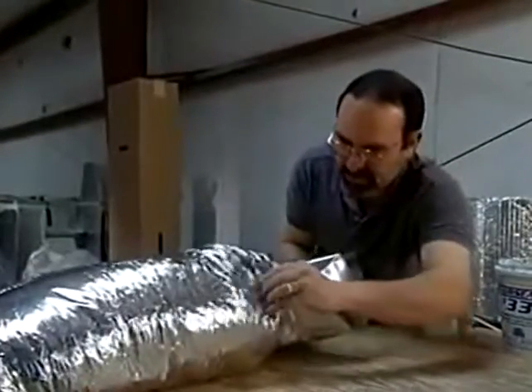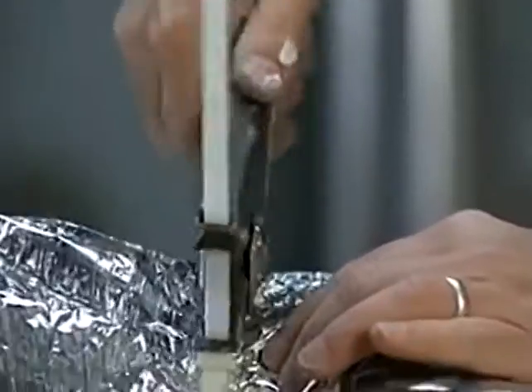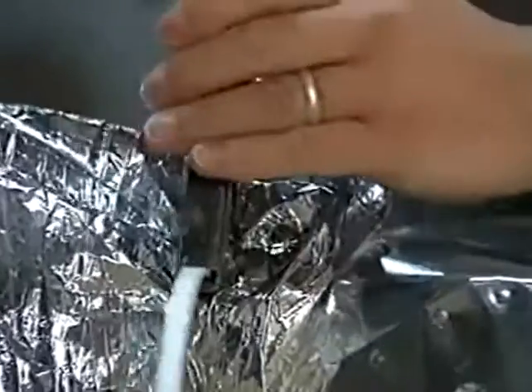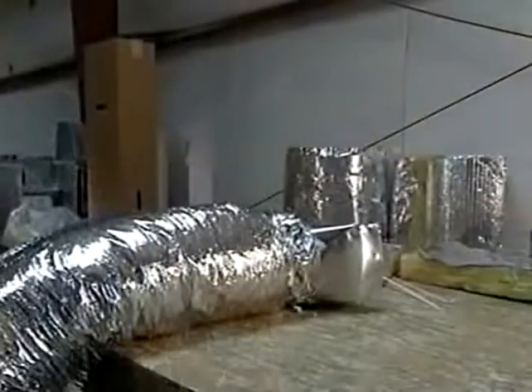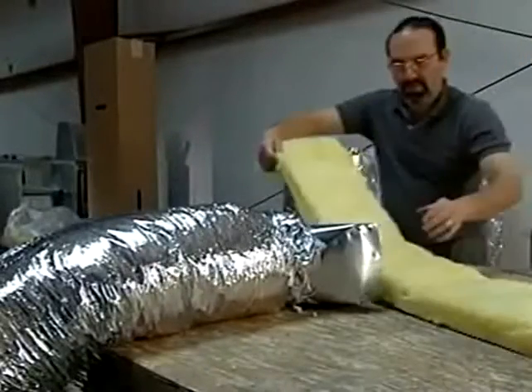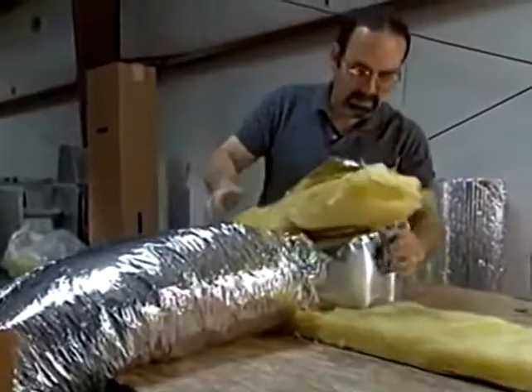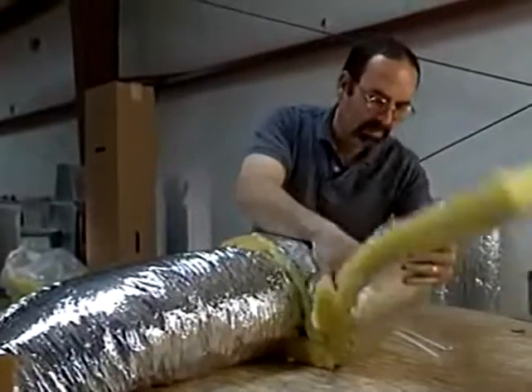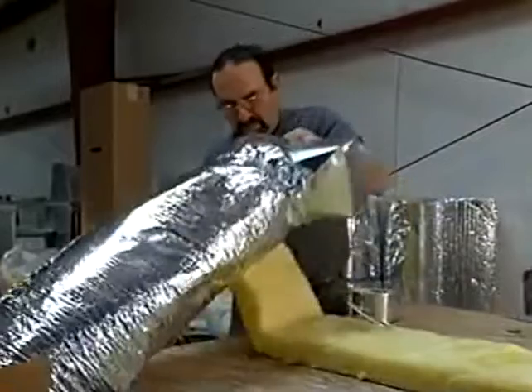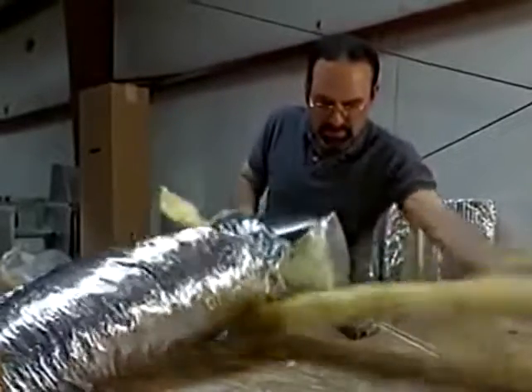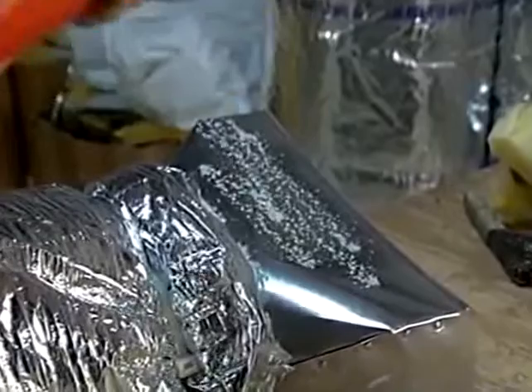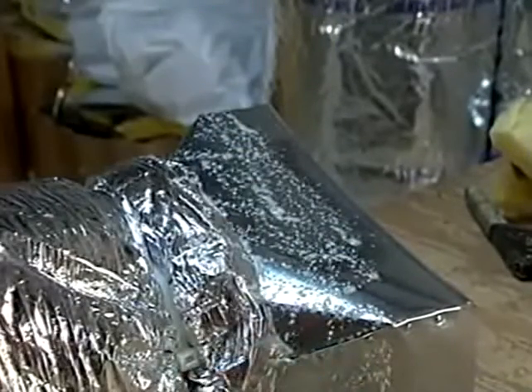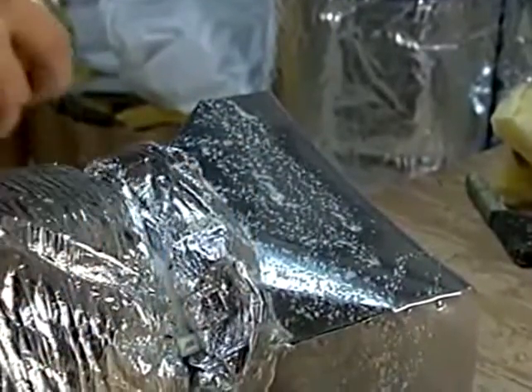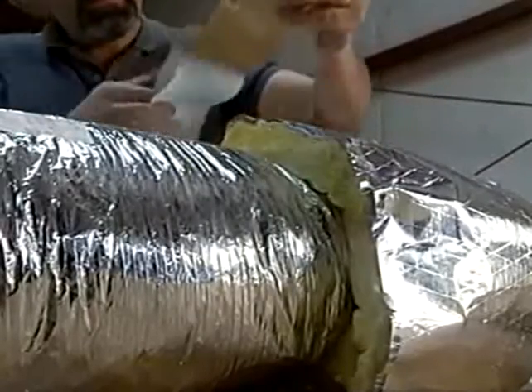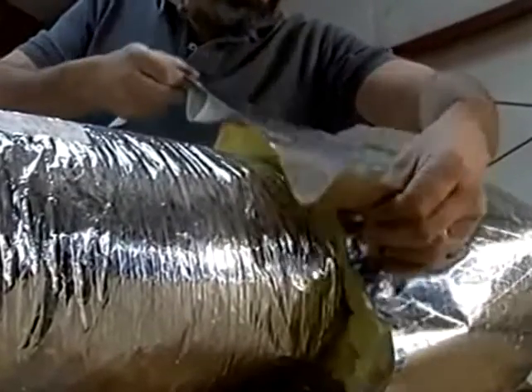He pulls the insulation back up over the liner and secures it with a collar tie. Insulating the boot itself is very important. Insulation helps eliminate condensation from developing on the metal surface of the boot, especially in the summer. First, measure the insulation and cut it to fit the entire depth of the boot. This contractor first sprays the boot with an adhesive to keep the insulation in place. He then attaches it to the boot using a UL 181 foil tape.